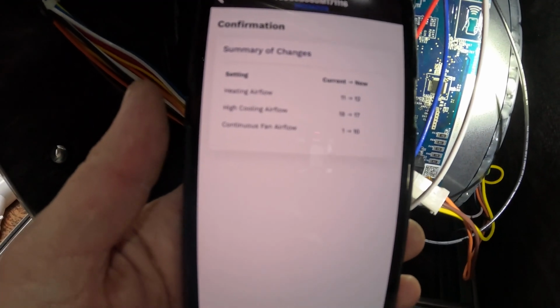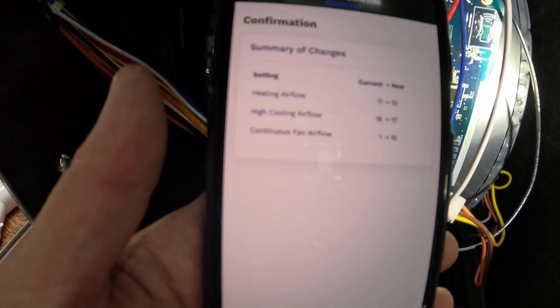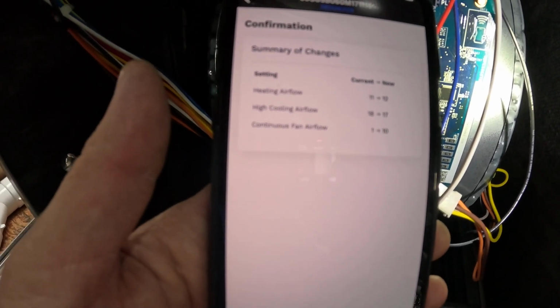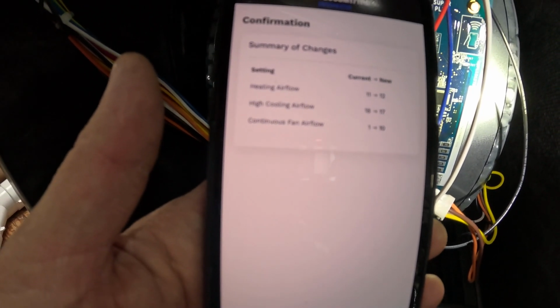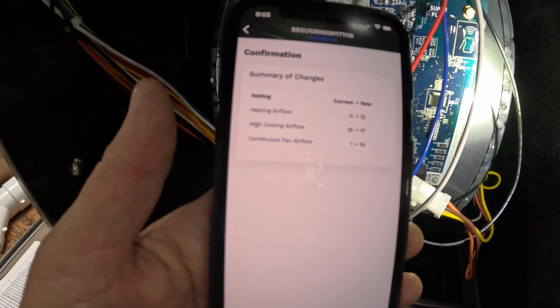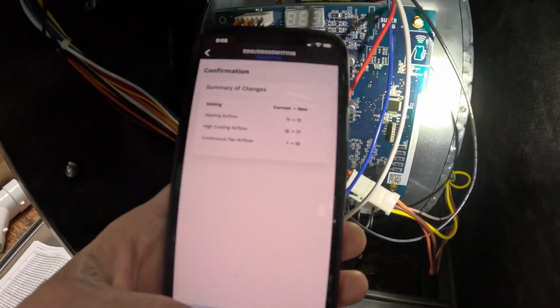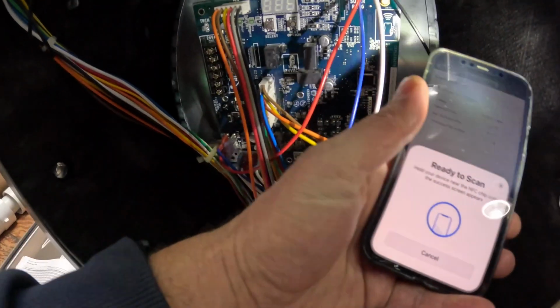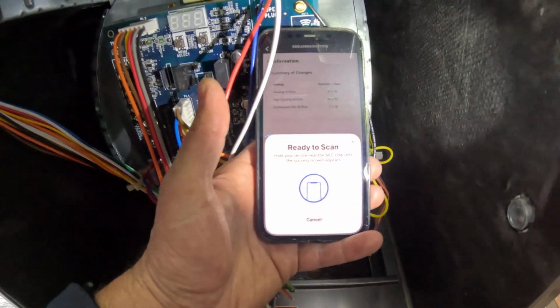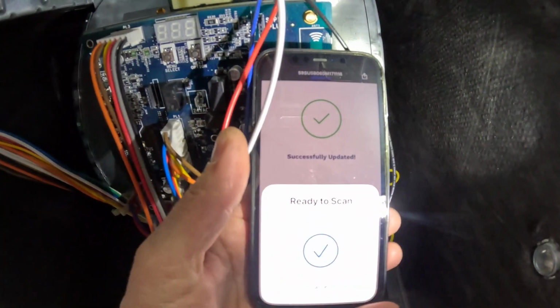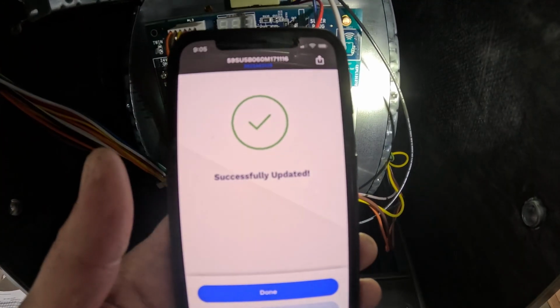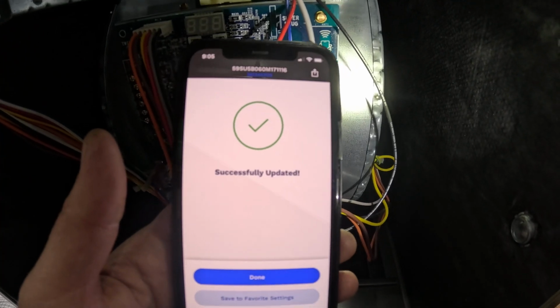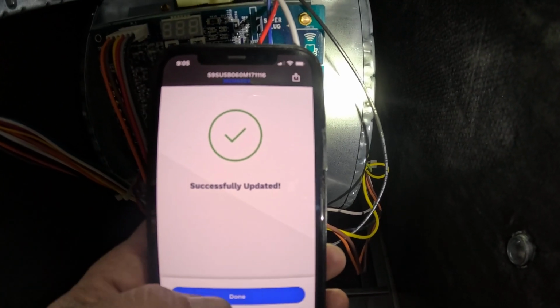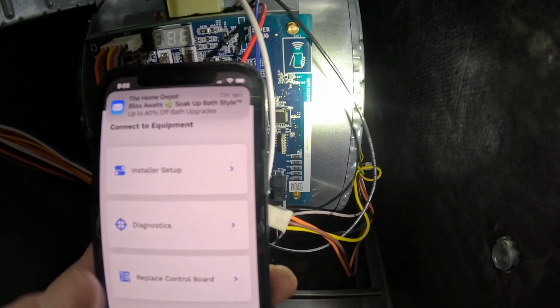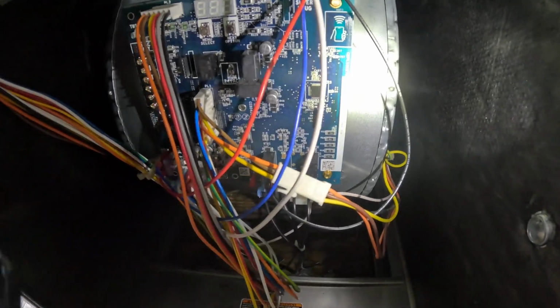It shows you your settings right there. So we've moved the heating airflow from 11 to 12, the cooling from 18 to 17, and the continuous fan airflow from 1 to 10. We're going to click continue. It says ready to scan, so we're going to hold it in there. It does say success, so that means it's locked in. Don't move the phone away. Leave it here for just a few minutes and select done, and we are all done with that.